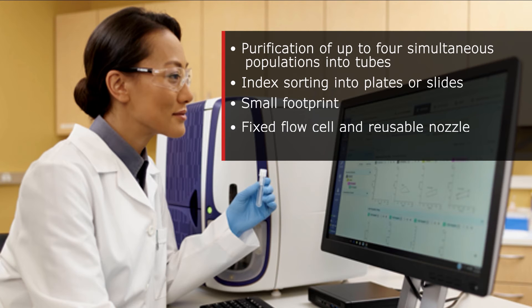Other features and capabilities of the BD FACSMelody cell sorter include purification of up to four simultaneous populations into tubes, index sorting into plates or slides, a small footprint, a fixed flow cell and reusable nozzle, so there's no need to purchase daily consumables.